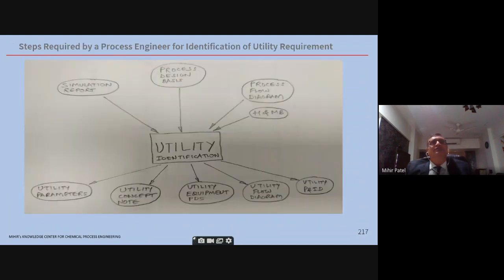Then the steps required by the process engineer for identification of utility requirement. Here you start from left to right. Utility identification is what is in the center. On the right, you have the simulation report as an input, then the process design basis, the process flow diagram, and finally the HMBD. All these inputs go into the utility identification. And what are the outputs coming from the process engineer? Again, from left to right: utility parameters, and a utility concept note is made, on how you are going to produce that utility. The utility equipment list and PDS are generated. A utility flow diagram is drawn, and finally the utility P&ID is drawn. So these are the various utility related parameters.